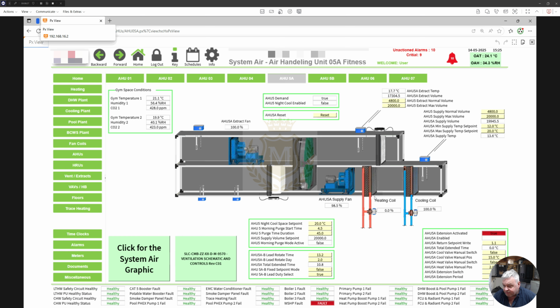So an air handling unit is normally, as I was saying, a unit that will take air from outside and will supply it into the office areas. And then each office area will have its own fan coil unit, and that will then treat the temperature lower or higher depending on what the user wants in that room. So we want to work on logic for the air handling unit. So let me just put you on pause and go back to the spreadsheet.